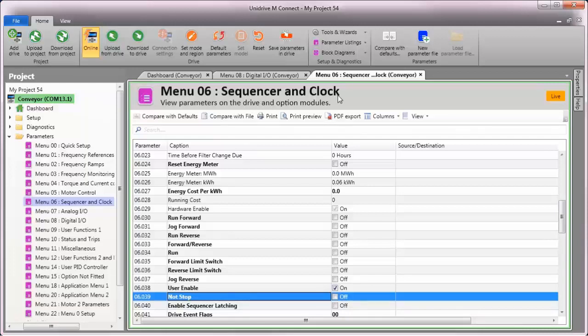It's called not stop because it uses inverted logic. In other words, when digital input number 7 is turned on, the drive will be in its not stopped, or running condition. When I turn input 7 off, the motor will come to a stop, and the drive will be in its stopped state.